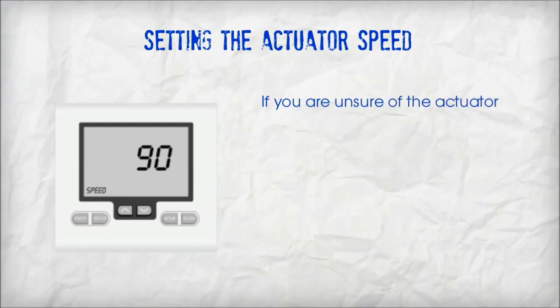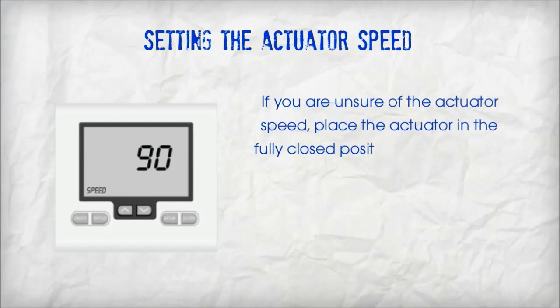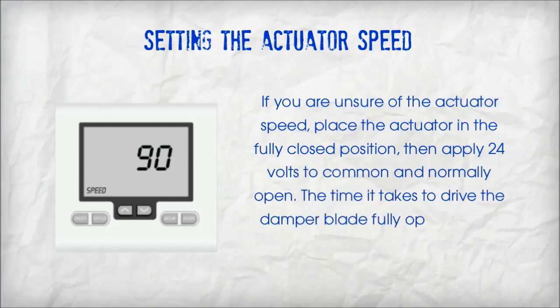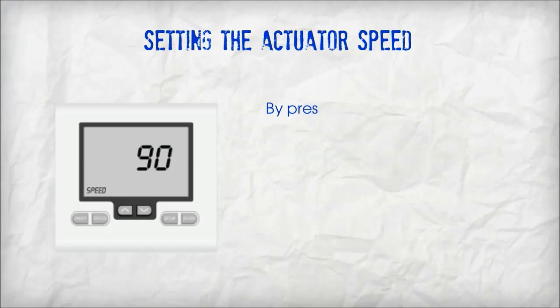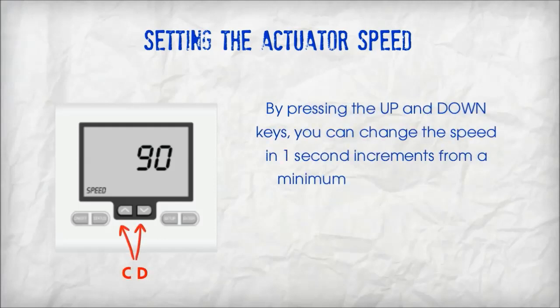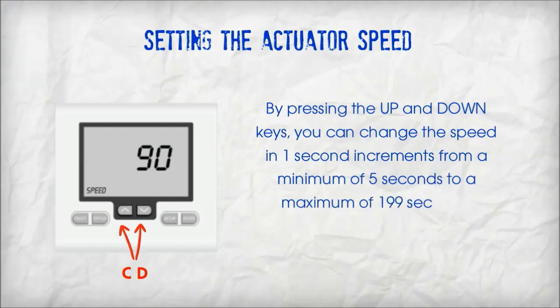If you are unsure of the actuator speed, place the actuator in the fully closed position, then apply 24 volts to common and normally open. The time it takes to drive the damper blade fully open equals the actuator speed. By pressing the up and down keys, you can change the speed in 1-second increments from a minimum of 5 seconds to a maximum of 199 seconds.